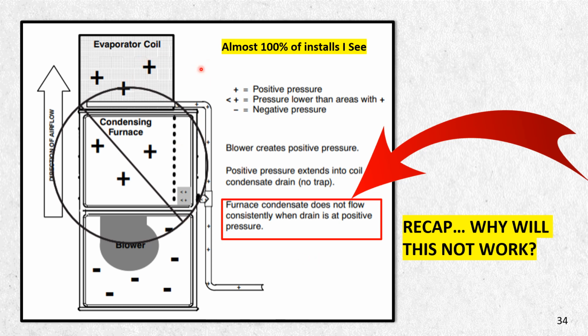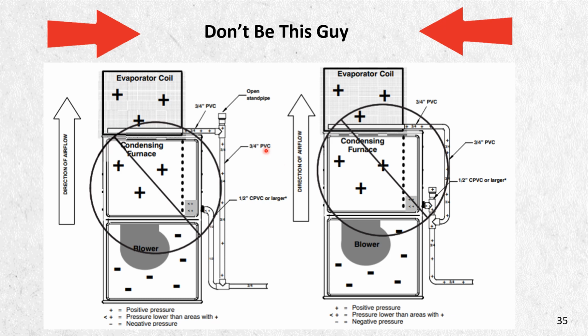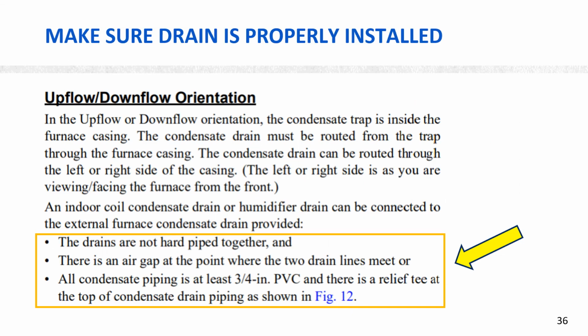Again, this is recapping. This is just about everything I see in the field. You cannot hard pipe that in with a condensing furnace. It has to have some kind of air induced into the system, or you're going to have water issues, mold issues, mildew issues. A lot of issues are going to happen from that. Here is where you can see that plus symbol there. That means there's a cap. Here there's no cap. So you got to introduce air to it.